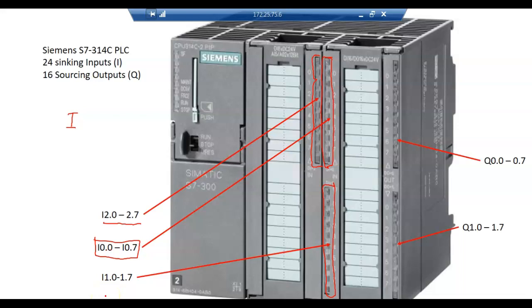PLCs, it depends on what you get. We call this guy a hybrid PLC, or I call it that. It's basically a modular PLC, which means we can expand it. A lot of these newer PLCs have some internal input-output on them, and then you can add more if you want. I don't know what Siemens calls their true rack-mounted ones, but we call them rack-mounted modular PLCs now. Allen Bradley does their ControlLogix, which is still a rack-mounted PLC.